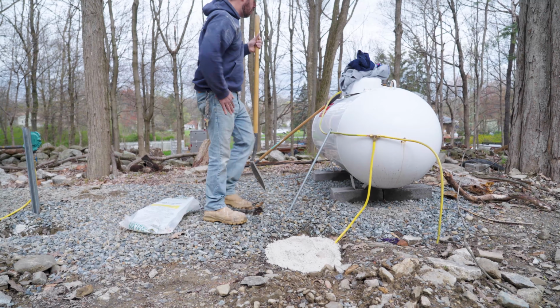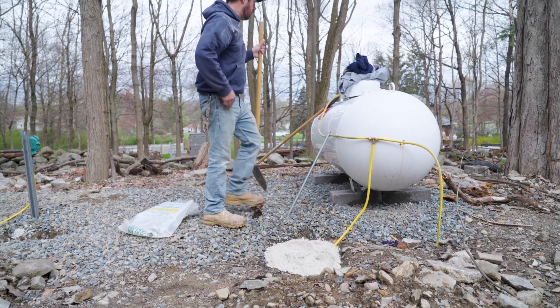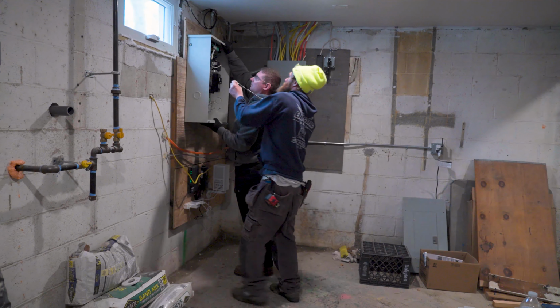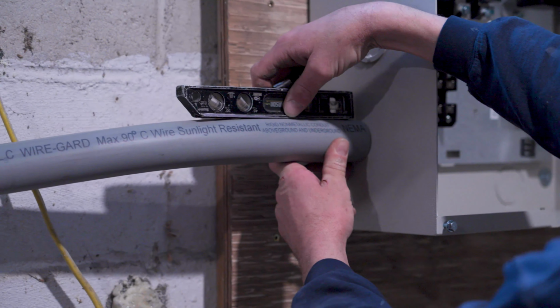To integrate a standby generator into the house, you need a couple of different things. The main thing is obviously the generator itself. You need a fuel source of some kind—in our case, that was a 300-gallon propane tank. You need an automatic transfer switch that ties into the panel, and load management modules that connect directly to whichever appliance you want to give priority. With all of those things installed, we now have fully automatic power to both the house and the shop.